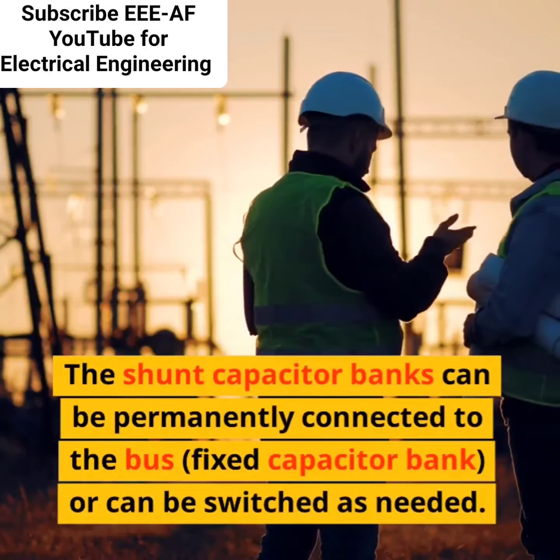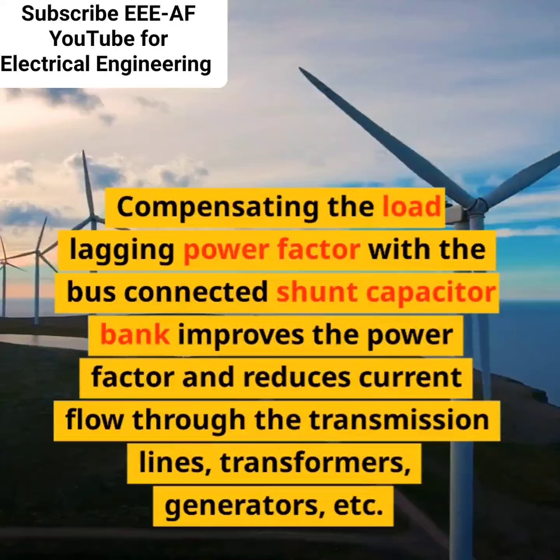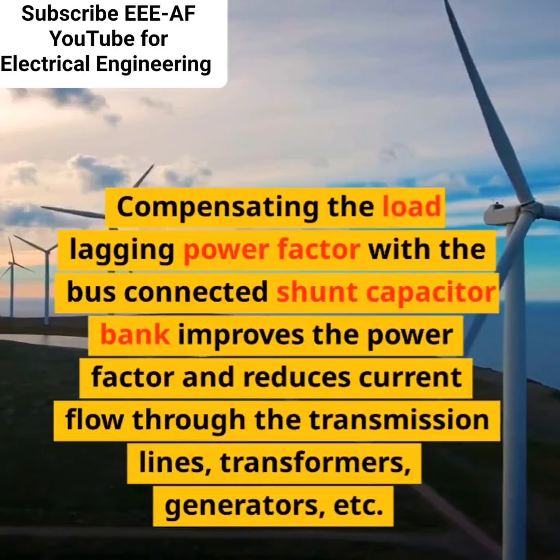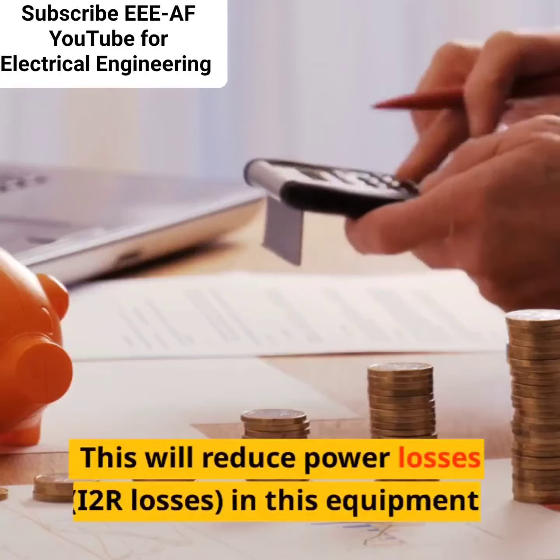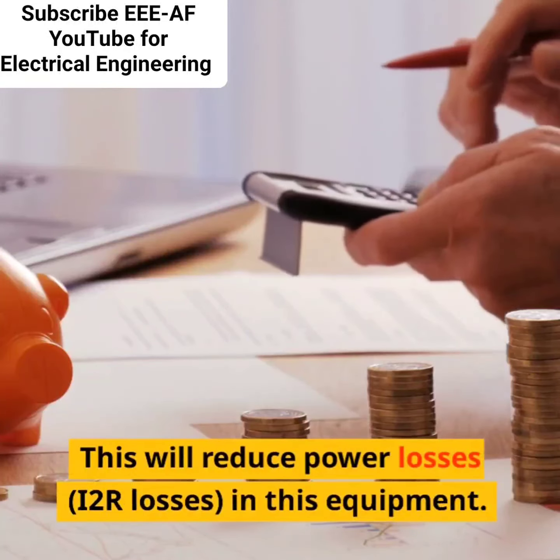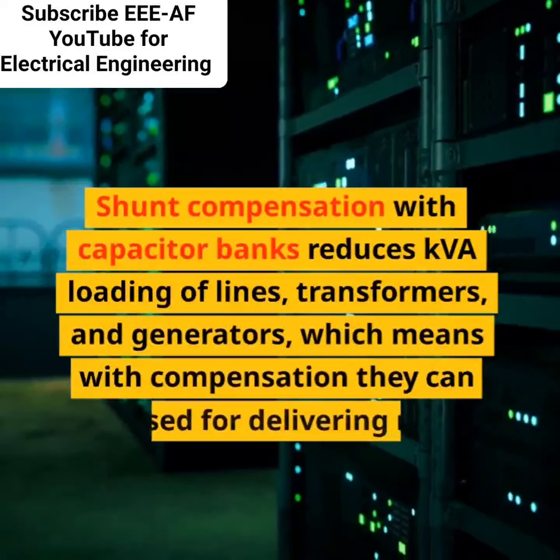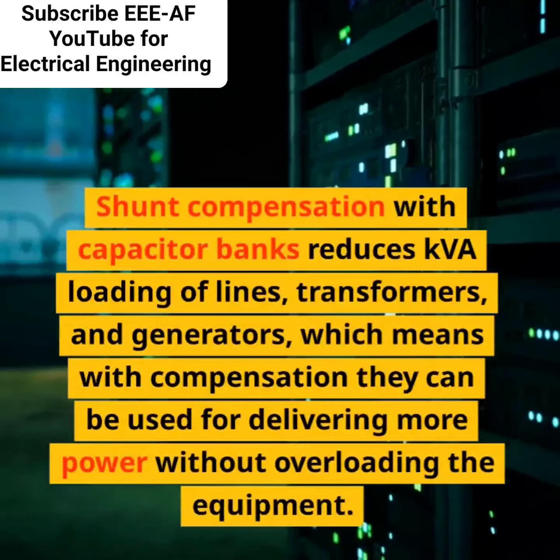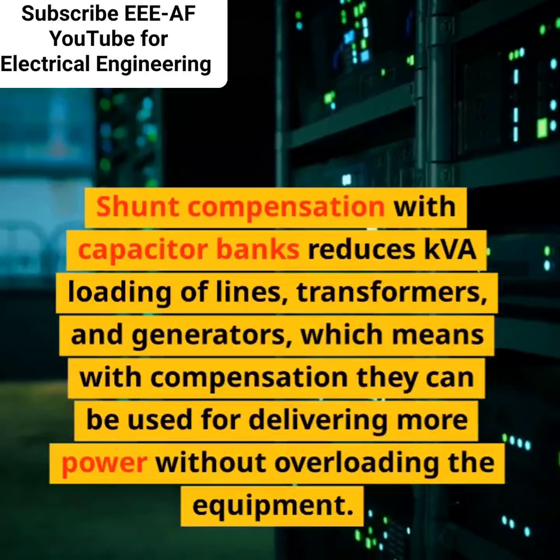Reducing power losses. Compensating the load-lagging power factor with the bus-connected shunt capacitor bank improves the power factor and reduces current flow through the transmission lines, transformers, generators, etc. This will reduce power losses, I2R losses, in this equipment. Increased utilization of equipment. Shunt compensation with capacitor banks reduces kVA loading of lines, transformers, and generators, which means with compensation they can be used for delivering more power without overloading the equipment.